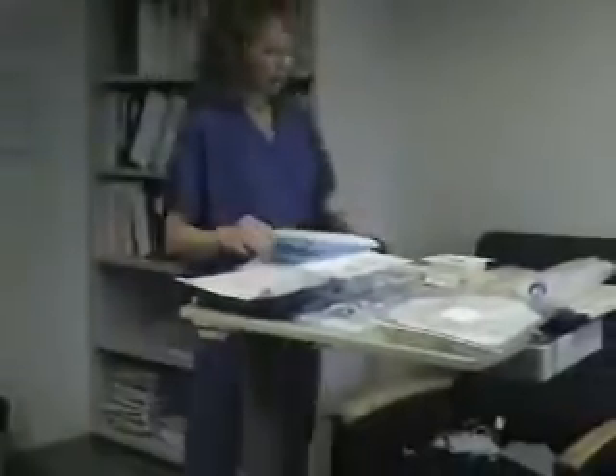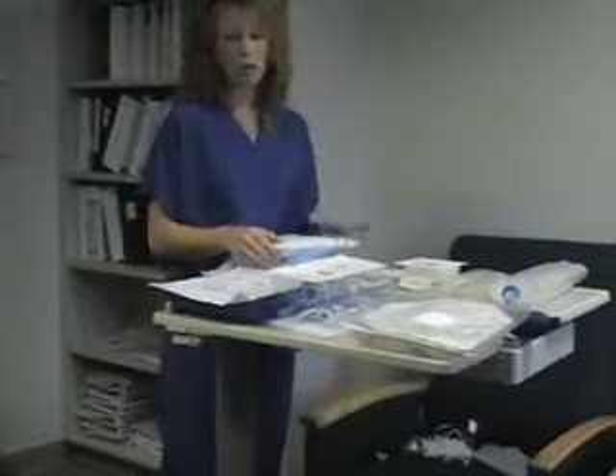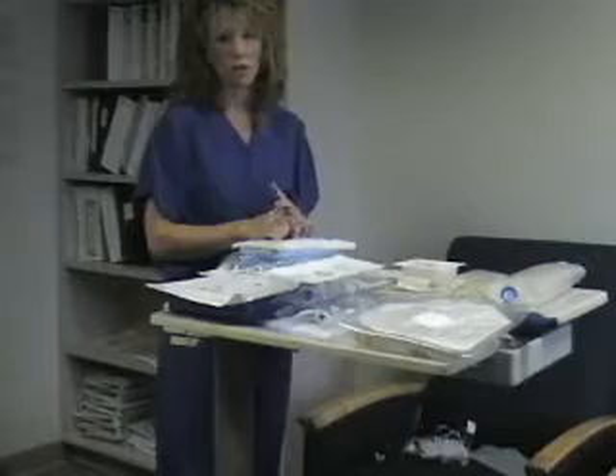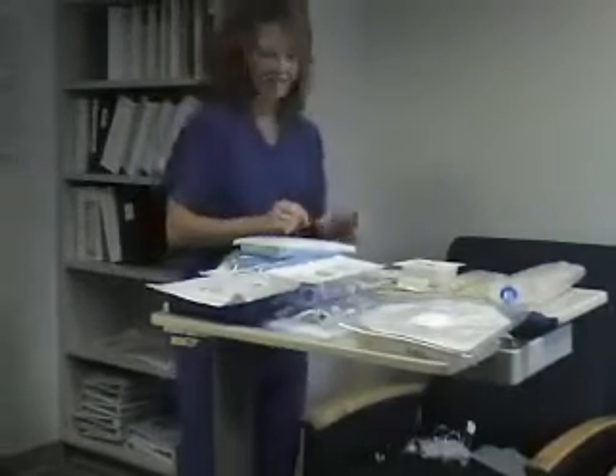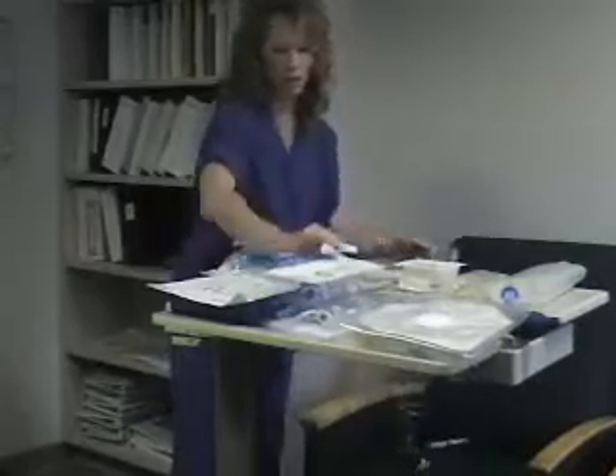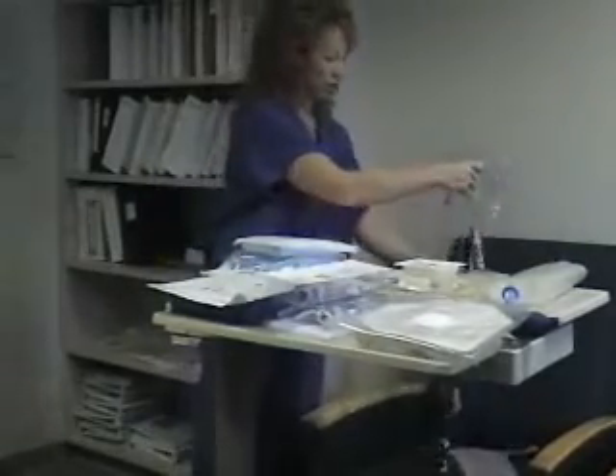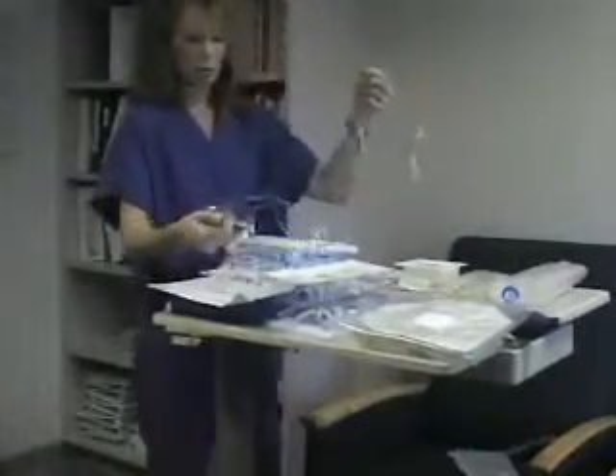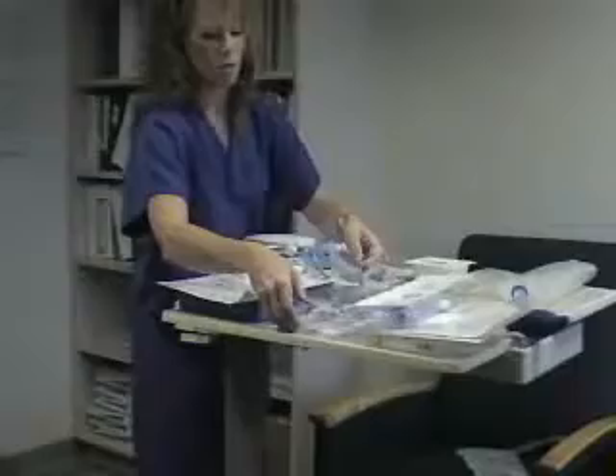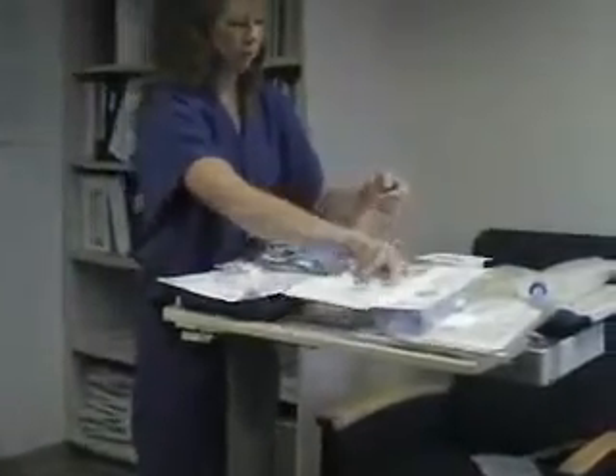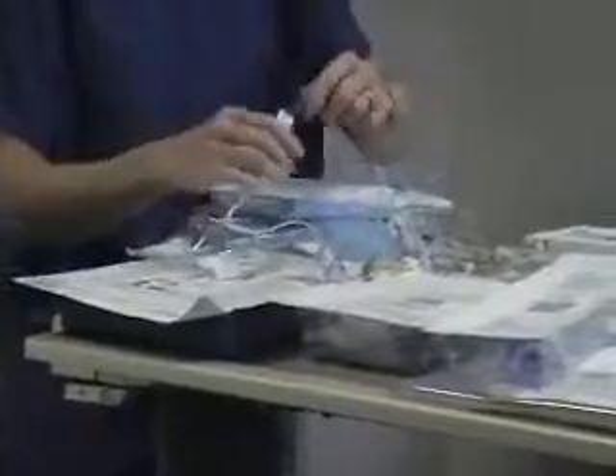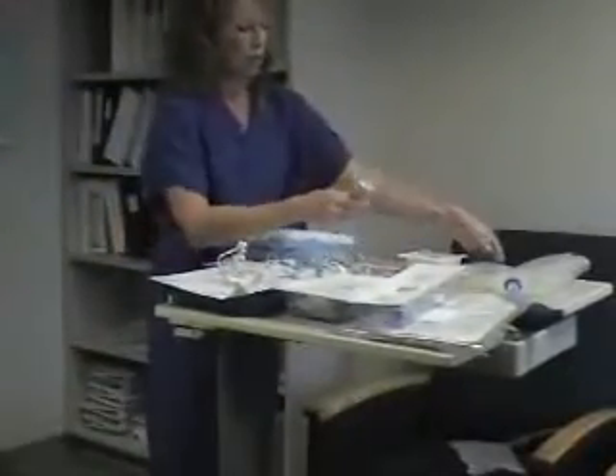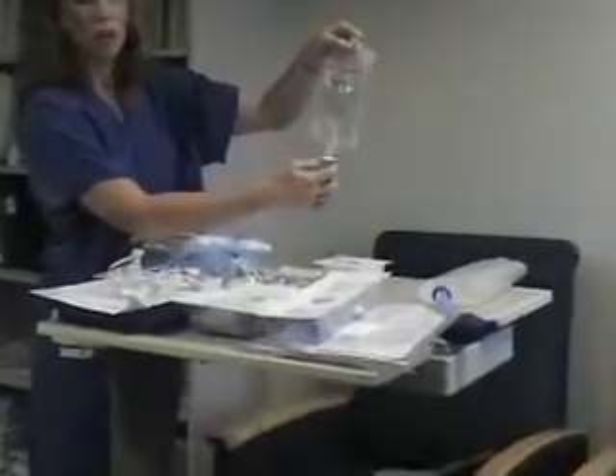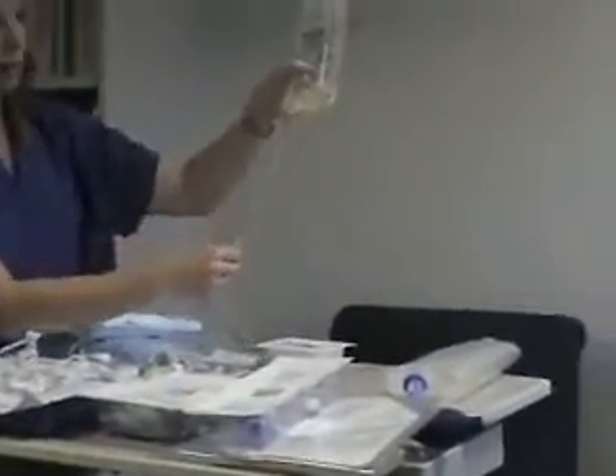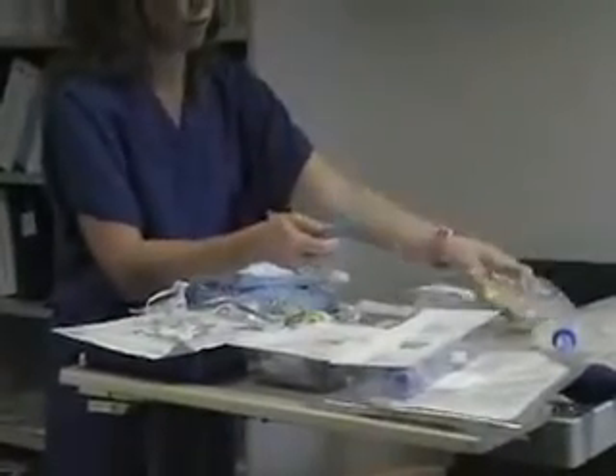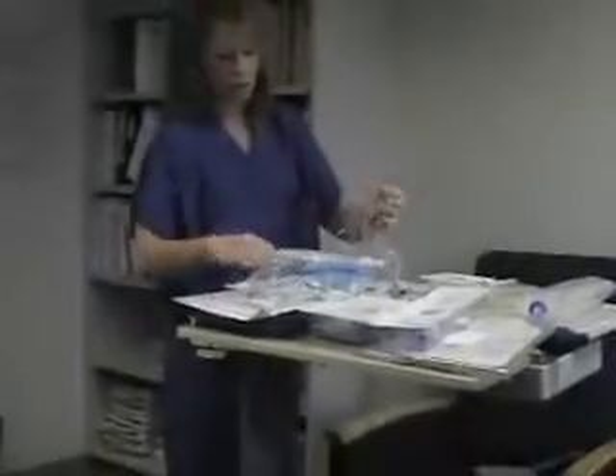What you need to do is prime all of your tubing. You'll of course need the modules for the monitor and the cable boxes. For demonstration purposes, I am not going to open these boxes, but your job to set up for this will be to prime these lines, which are inside the box of the bifurcated Transpac monitoring system. And you will need to prime these lines with the heparinized saline. You will spike the saline bag. You don't need to put it in its pressure bag at this point. Spike the saline bag, and it's helpful if you are able to hang this for gravity flow. And you're going to prime all of this tubing.